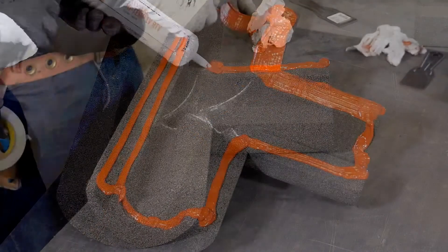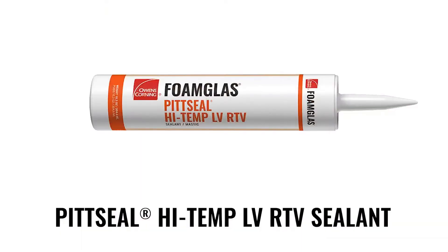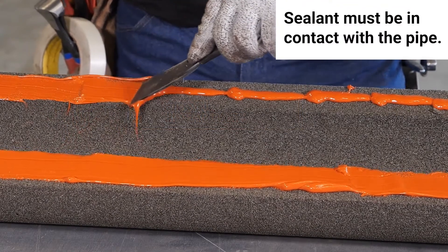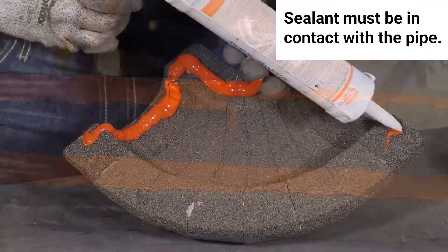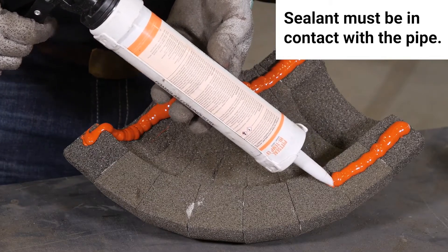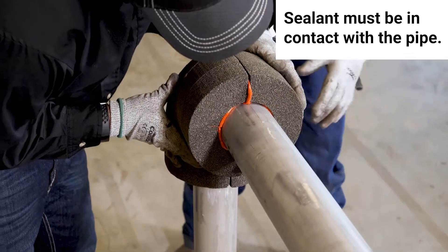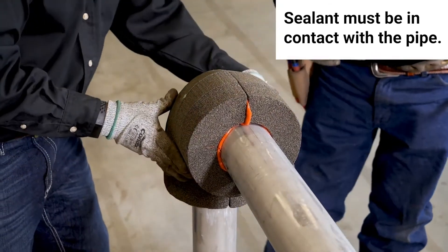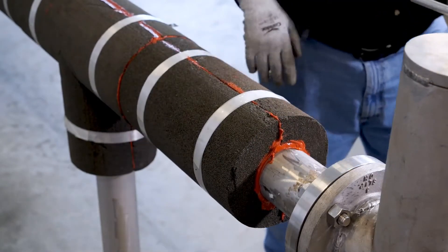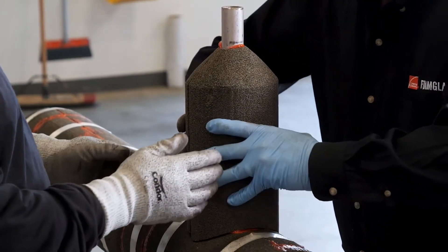On the foam glass sealed system, the joints are to be fully sealed using Pittseal High Temp LV RTV sealant from the exterior of the insulation down to the pipe. This one-part neutral cure sealant is formulated for use with foam glass insulation. The lower viscosity of the sealant enables efficient spreading and sealing. It cures to an elastomeric solid at room temperature and is designed to accommodate most expansion and contraction when applied according to specifications.